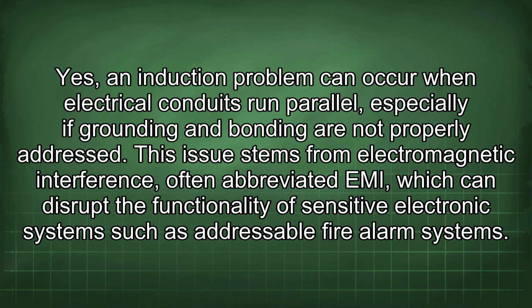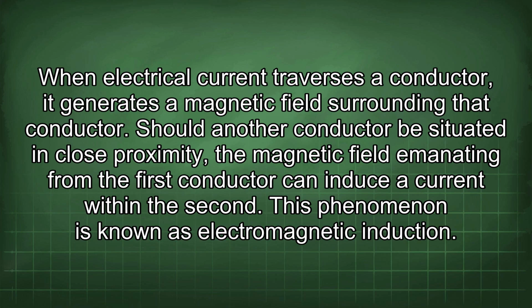Yes, an induction problem can occur when electrical conduits run parallel, especially if grounding and bonding are not properly addressed. This issue stems from electromagnetic interference, often abbreviated EMI, which can disrupt the functionality of sensitive electronic systems such as addressable fire alarm systems. When electrical current traverses a conductor, it generates a magnetic field surrounding that conductor. Should another conductor be situated in close proximity, the magnetic field emanating from the first conductor can induce a current within the second. This phenomenon is known as electromagnetic induction.